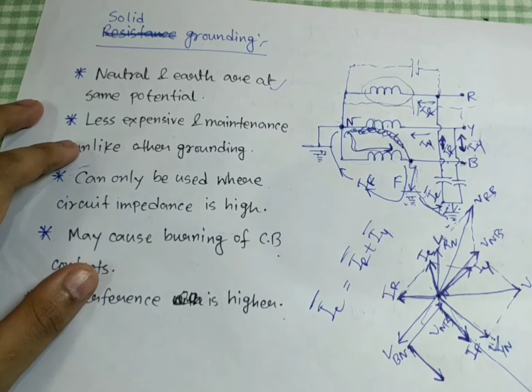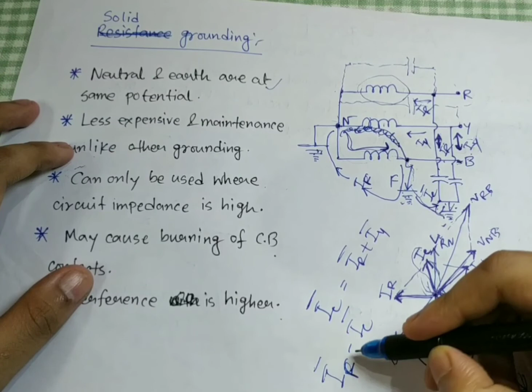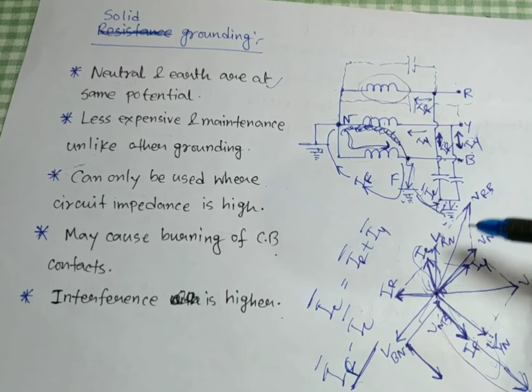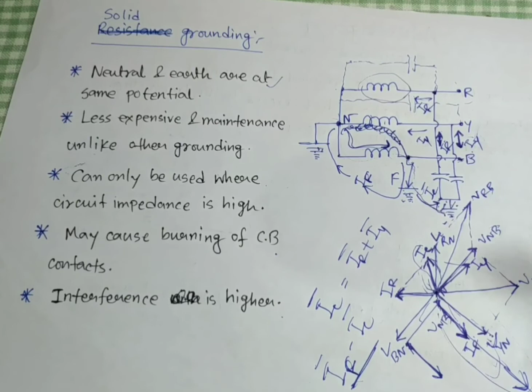If this component is completely vanished, the arcing phenomena will also be gone, because whatever arcing takes place is only due to this capacitive current IC, which is responsible for the arcing ground. So this large magnitude of fault current completely nullifies this component, and the resultant of IF and IC is the resultant fault current that flows during the fault. Since there is no capacitive current, the arcing phenomena is also gone. That is why I said that by this grounding concept we can prevent the arcing phenomena.